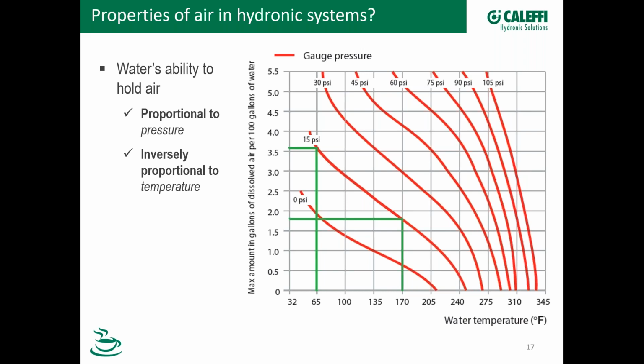For example, let's say that we have a boiler system that's charged up to 15 psi, so that's this red line right here. And we have cold water, 65-degree water coming into that boiler. At 15 psi, the properties of that water in terms of holding air are about 3.6% can be dissolved. In other words, if you had 100 gallons of water, 3.6 gallons of that would be air. Now, as we heat that water up, we come down this red line right here. We drop down this red line. When that water reaches 170 degrees, the property drops to about 1.8, which is half. So then in that 100 gallons of water, about 1.8 gallons of it are air.